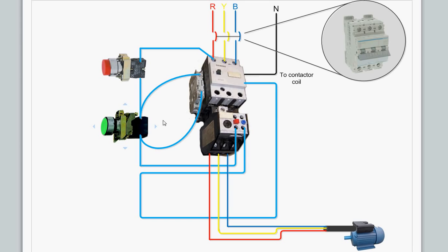So when the person presses the start button here, it closes the complete circuit through this one, and once the contactor is activated, at that time the motor starts here, and this is the hold on contact. This is a normally open contact. So once the circuit is activated, the current flows from the stop button and goes here. Now it is a closed contact, so it comes back here and continues through this path, and the motor keeps running.